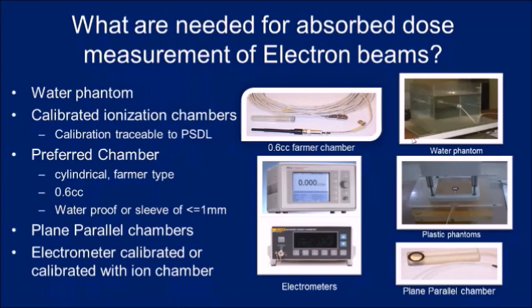What is needed for absorbed dose measurements of electron beams? It is very similar to photon but with some differences. You need a water phantom and calibrated ionization chambers, with calibration traceable to PSDL. The preferred chamber is a 0.6 cc cylindrical chamber, waterproof or with a waterproof sleeve, and also a plane parallel chamber, which is required for low energy electron beams. You also need electrometers, either calibrated with the ion chamber or with a calibration factor, and a plastic phantom.